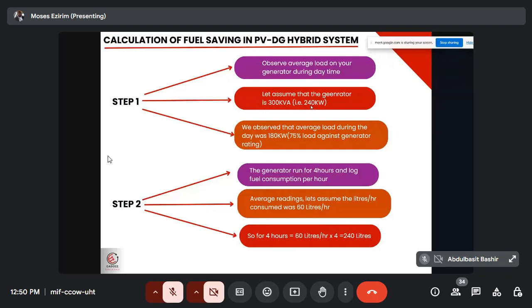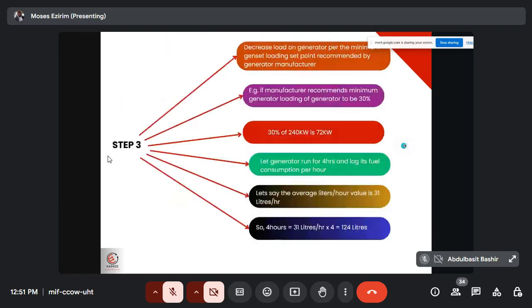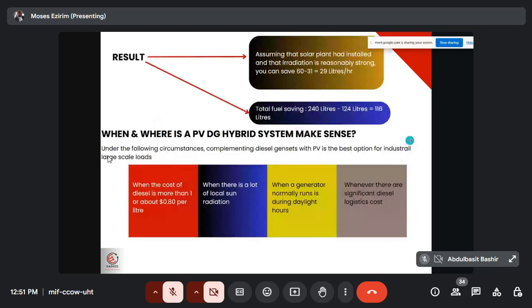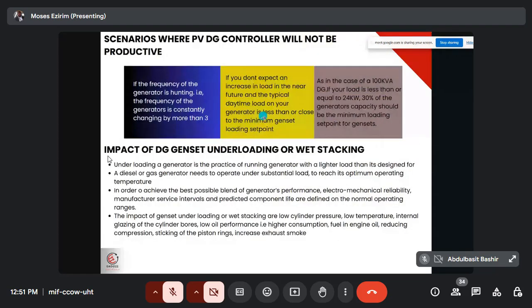Now, if the manufacturer is recommending a minimum genset loading of 25%, what would be the base load of this generator? I need someone to tell me. What is the base load of the generator? If the OEM of the generator is recommending 25%, what would be the base load? 60 kilowatts, right? So that's the base load. Now let's come to this. Let's assume that you've done your audit, and you realize that the client's average load is, let's say, 50. This is a waste of money.